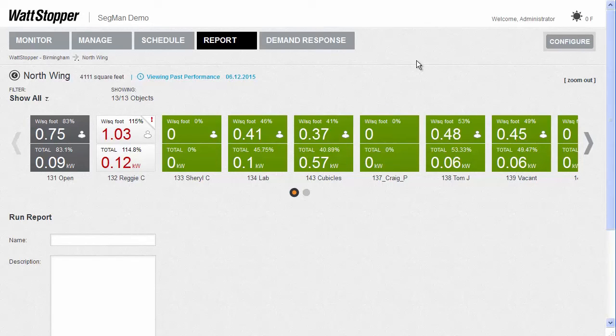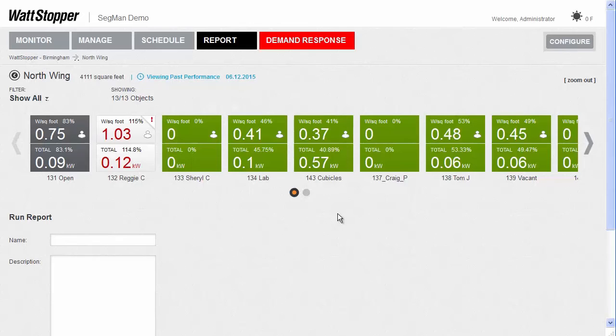We've got a very easy way to generate that demand response signal. When I click this tab, I can choose to send the demand response as a force condition — meaning it can't be overridden, which is typical — or as an override condition, which is helpful for testing since people in the space can override the demand shed if they want to. I can actuate the demand response for the entire building or just for an area. Note that the demand response tab has now turned red, making it very clear we're in demand response mode until I come back and disable the DR signal.